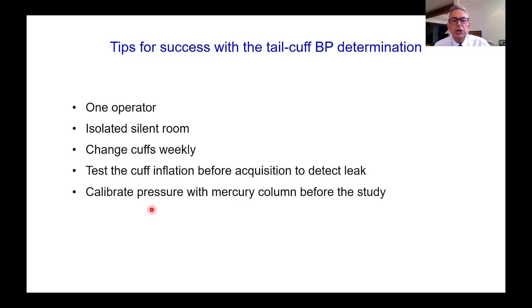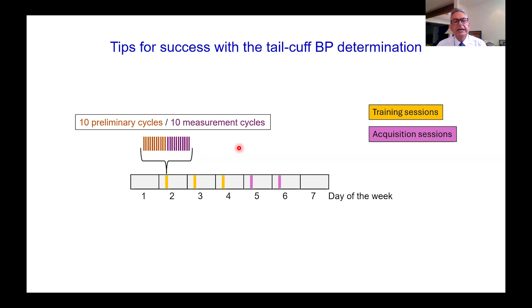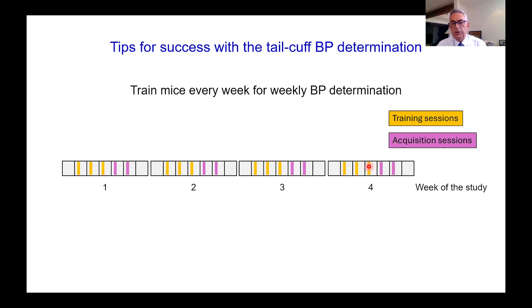You should train the mice on 3 consecutive days at least to get 2 measurement days. The measurement should be done all at the same time of the day. It's better to do it early in the morning. In each session, you should do 10 preliminary cycles to let the animal adapt to the machine and warm up, and then 10 measurement cycles. If you do weekly blood pressure, you need to repeat the training.